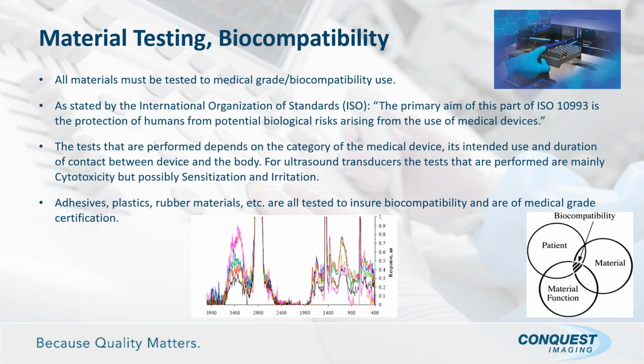So you test these for biocompatibility, making sure your materials are of a medical grade. And that goes right down to the fourth bullet point there. Even your adhesives and your plastics, and I mentioned the silicone rubber materials, everything needs to be of a medical grade, and you want to have the items biocompatibility tested. And the manufacturers have to do this: once they complete their probe assembly, it gets tested for biocompatibility as a whole, so that the various materials and any chemicals used in the manufacturing process do not turn this into a device that fails biocompatibility testing and could be harmful or cause some sort of irritation to the patient.